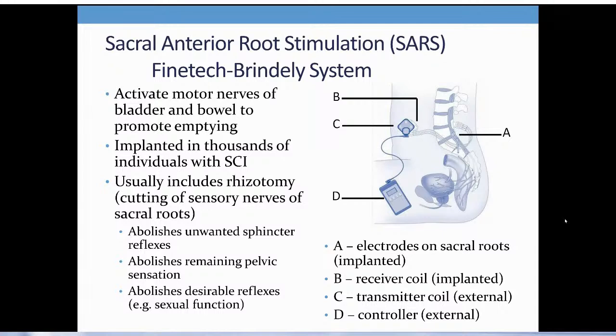So if you meet someone with this device, you won't know they have it in them, because you're not going to see wires sticking out of them. They'd have to show you the very small bulge that is that receiver coil under their skin, and that's going to be pretty discreet. When they want to empty their bladder, this is also for emptying bowels or for improving sexual function. Those are also indicated here. But when they want to empty, they'll put the transmitter coil, C, on the skin on top of where the receiver coil B is. And so they'll get transmission through the skin, coil to coil, using a magnetic inductance transmission of power.